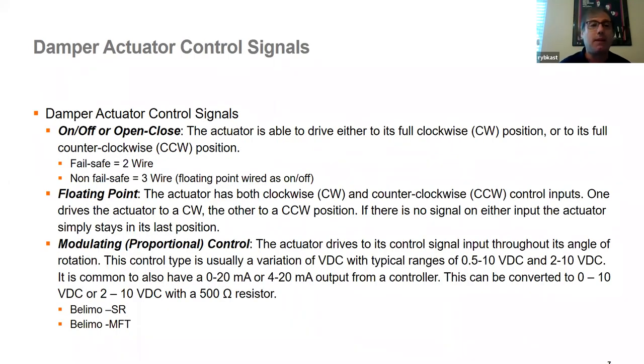The three most common control signals are: on-off or open-close for two-position isolation applications; floating point, like on a VAV box; and proportional control, with 2-to-10 volts DC being our dash-SR offering. We also have multi-function technology, or dash-MFT, which is a configurable field input. It ships from the factory at 2-to-10 volts DC, but you can use our ZTH handheld tool or PC tool to change the input signal parameters to whatever you need — for example, 6-to-9 or 0-to-10 volts.